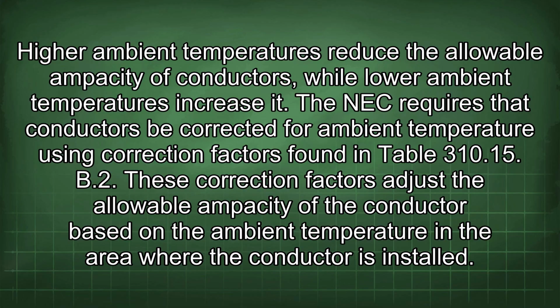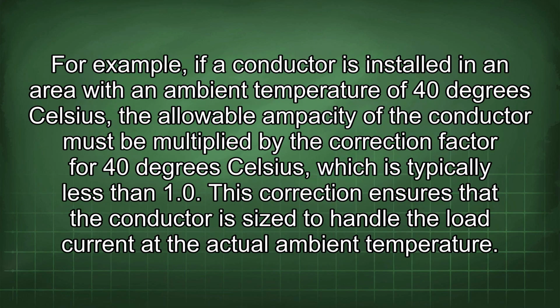the conductor is installed. For example, if a conductor is installed in an area with an ambient temperature of 40 degrees Celsius, the allowable ampacity of the conductor must be multiplied by the correction factor for 40 degrees Celsius, which is typically less than 1.0. This correction ensures that the conductor is sized to handle the load current at the actual ambient temperature.